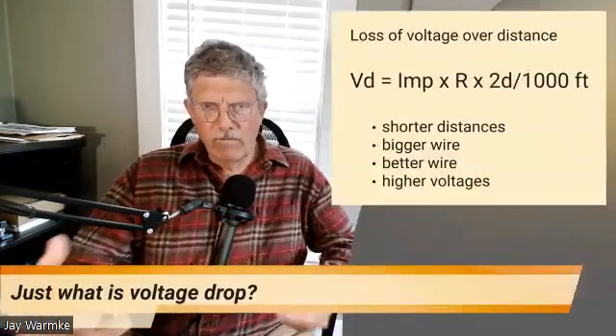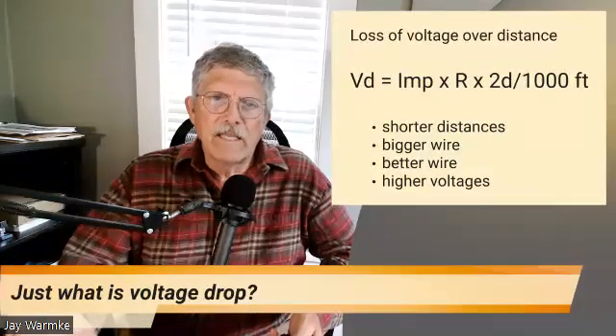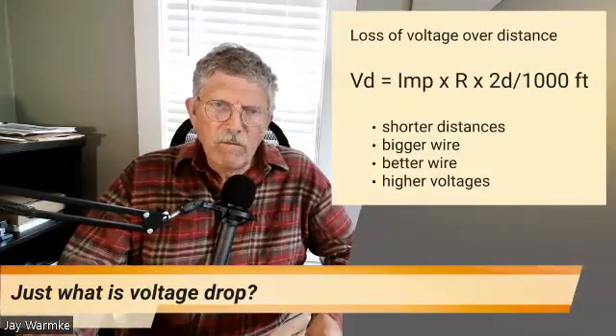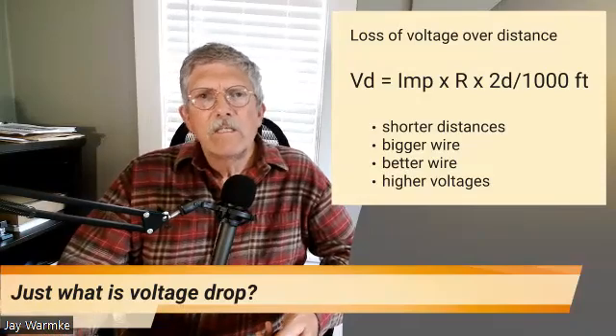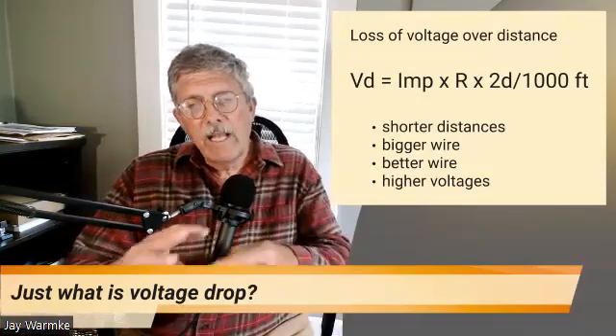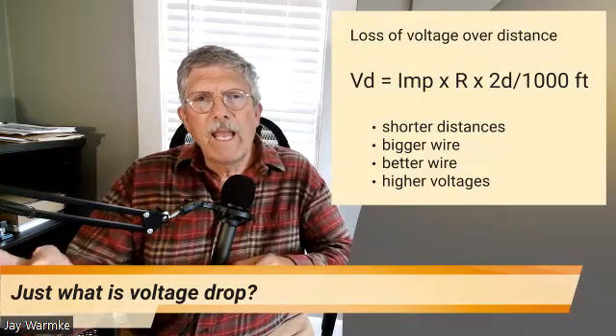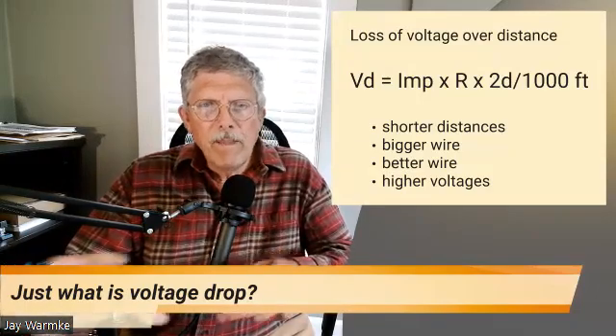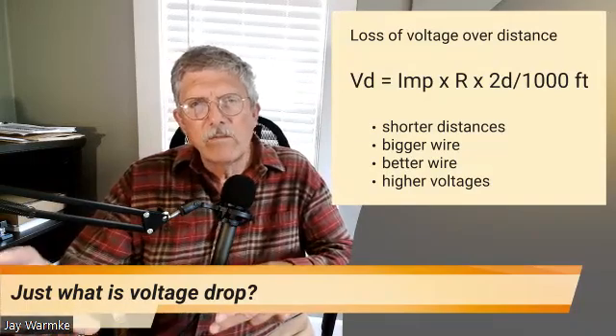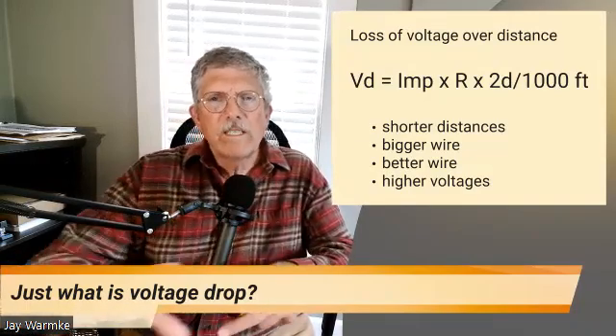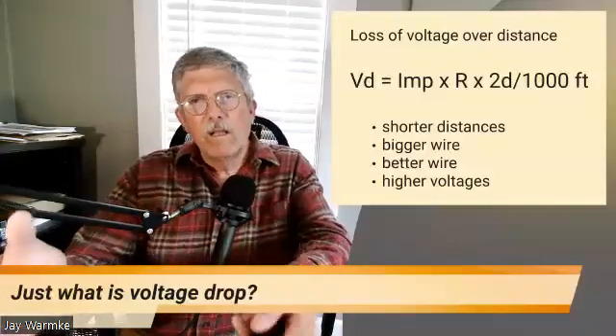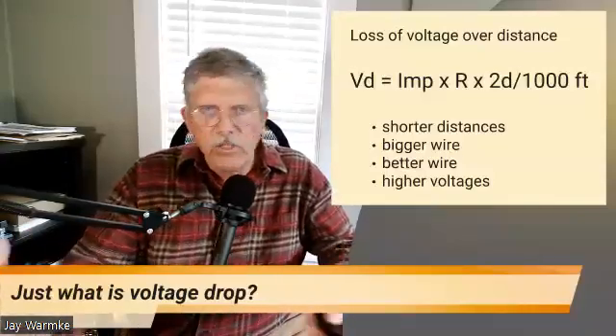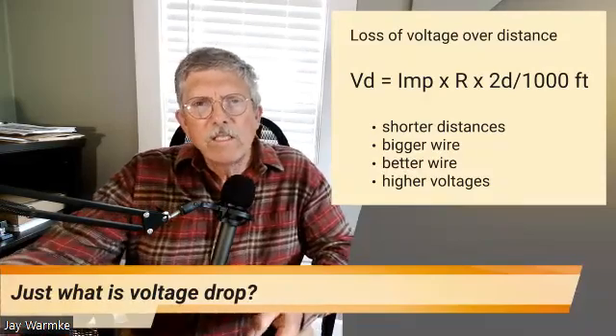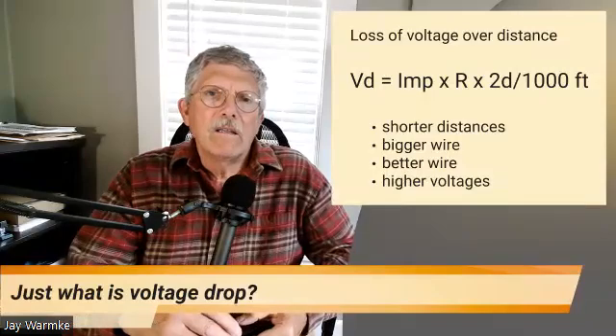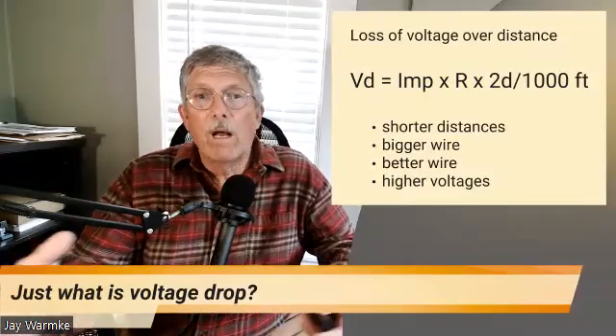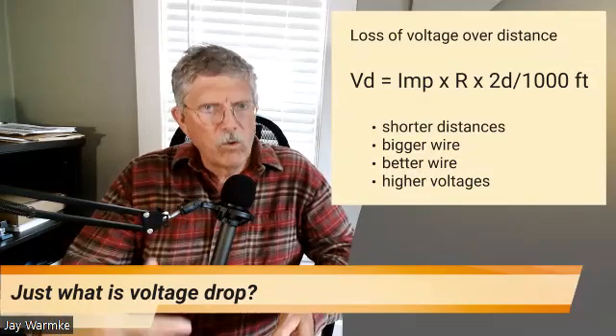So first off, what is voltage drop? That is the loss of voltage over distance due to resistance. The analogy is a water pipe, where the pressure it operates under is the voltage. Over distance, the friction of the water moving along the side of the pipe will cause the pressure to decline. Likewise, over distance, the friction or resistance that the wire imposes upon the electrical signal will cause voltage to decline.